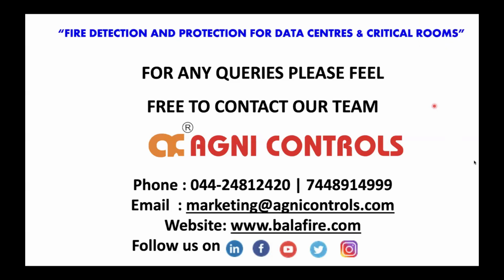The room integrity test is conducted using a door fan test. That's what they normally do. The room is pressurized and depressurized, with pressure of about 10 pascals up to 60 pascals. Multiple readings are taken, and sensor readings are taken, determining the leakage index. The door fan test is also done in areas where windows, partitions and glass doors are used. So yes, it can be used, but it also depends on what type of glass it is, what the thickness is, and what amount of pressure it can withstand. That is a consideration that needs to be taken.